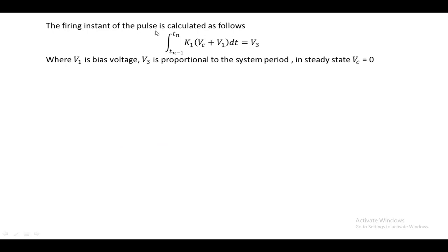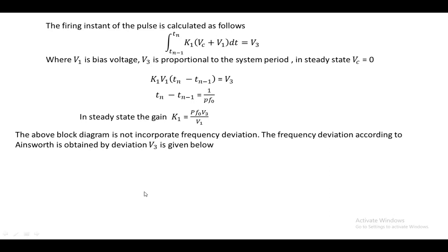At a firing instant, the pulse is calculated as: integral from TN-1 to TN of K1·(Vc + V1) dt = V3, where Vc is the control voltage, V1 is the bias voltage, and V3 is proportional to the system period. In steady state, Vc = 0, and completing the integration gives K1·V1·(TN − TN-1) = V3. Since TN − TN-1 = 1/(P·f0), substituting this allows calculation of gain K1. In the above block diagram, if any frequency deviations exist due to a disturbance, they are not taken into consideration; however, they can be accounted for when generating pulses to the valve.